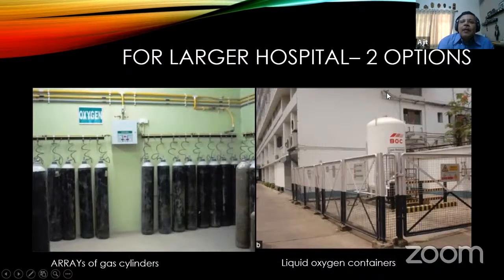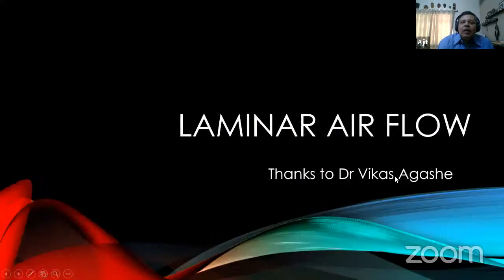For larger hospitals, there are two options. One is an array of gas cylinders where you have two different sets of gas cylinders. When one is supplying oxygen, the other is on standby. When this runs out, the standby takes over by automatic switchover and you have to change the cylinders. The bigger theaters and bigger hospitals now have a liquid oxygen container which is filled directly with liquid oxygen and supplies oxygen to the whole of the hospital.